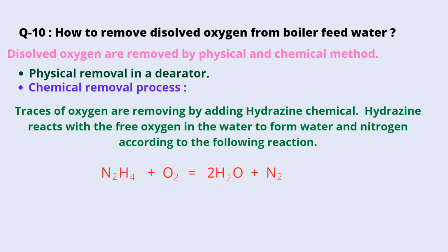How to remove dissolved oxygen from boiler feed water? Dissolved oxygen is removed by physical and chemical methods. Physical removal is done in a deaerator, and then the chemical removal process. Traces of oxygen are removed by adding a hydrazine chemical. Hydrazine reacts with the free oxygen in the water to form water and nitrogen according to the following reaction. Hydrazine reacts with oxygen to form water and nitrogen.